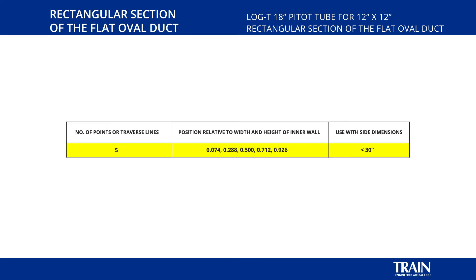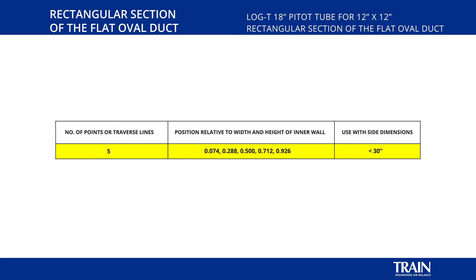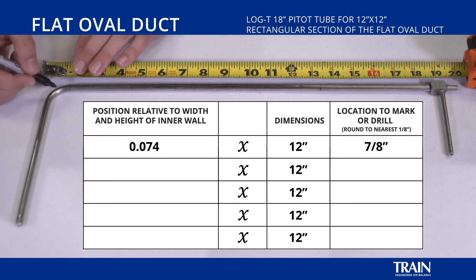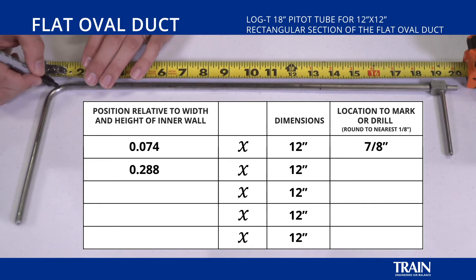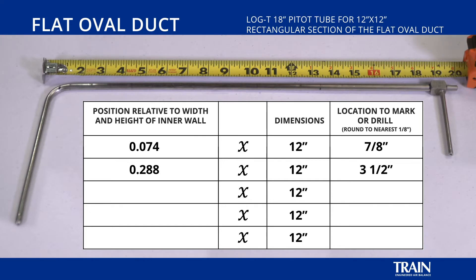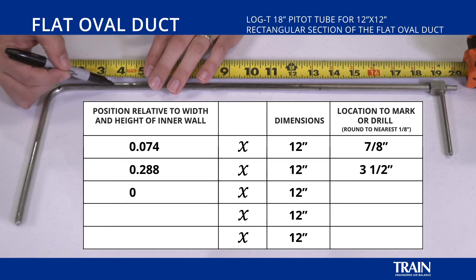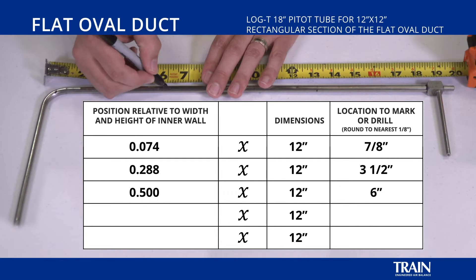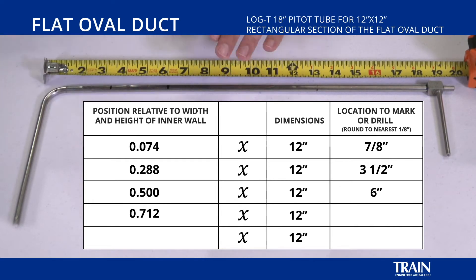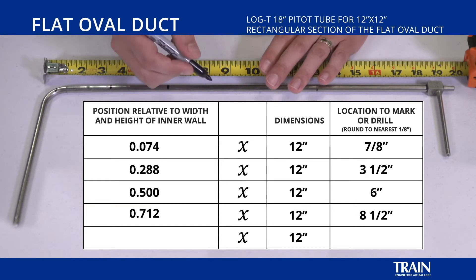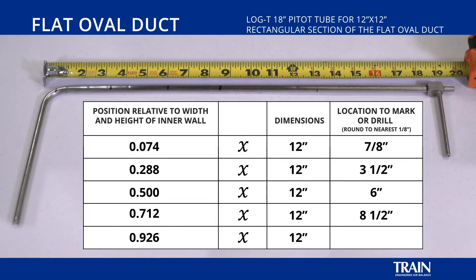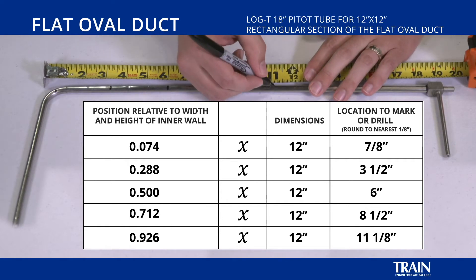The first point to mark for a 12 inch duct is 0.074 times 12 inches, which results in seven eighths on the pitot tube. The second factor is 0.288, which results in three and one half on the pitot tube. The third factor is 0.50 multiplied by 12 inches, giving us six inches on the pitot tube. The fourth factor, 0.712, again multiplied by 12 inches, gives us eight and a half on the pitot tube. And finally, the last factor is 0.926, again multiplied by 12 inches, results in 11 and one eighth on the pitot tube.